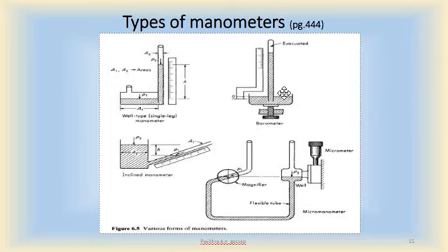The pressure in the evacuated portion, so this is the evacuated portion of the barometer, is not really absolute zero, but rather the vapor pressure of the filling fluid, mercury, at ambient temperature. That is, in this evacuated portion we do not have absolute zero pressure, but the pressure present here will depend upon the ambient temperature of the liquid filled in this column.